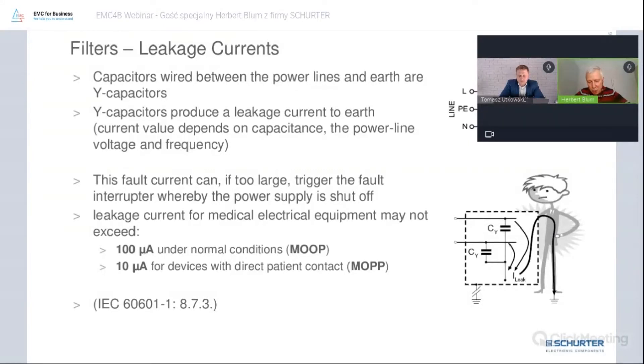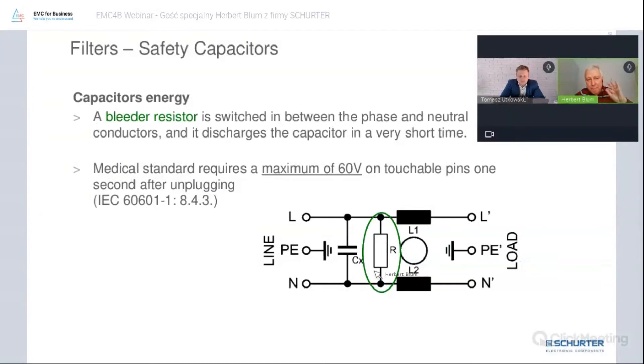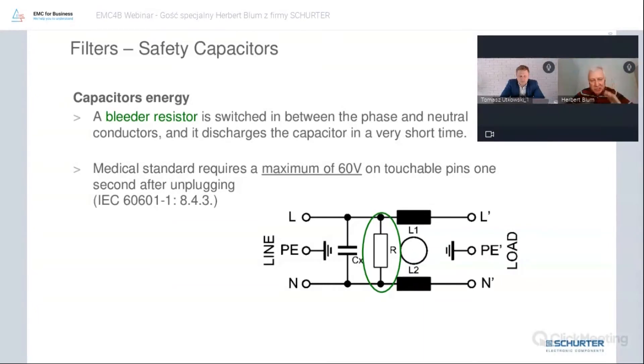If you have a double ground connection or a very low impedance ground connection, it is really critical. That is where a bleeder resistor is used — it is simply there to discharge the capacitors.